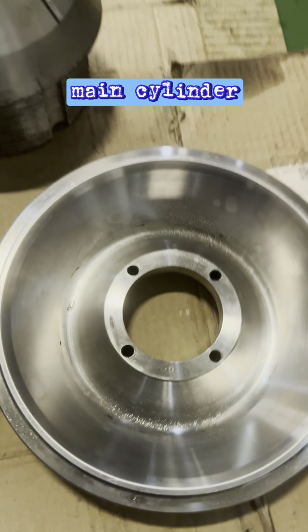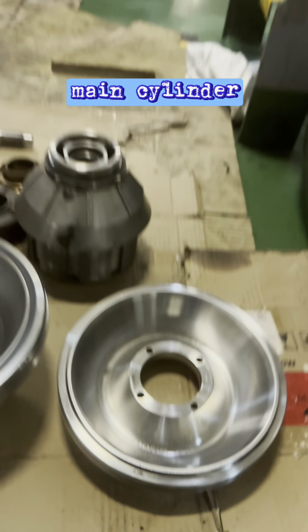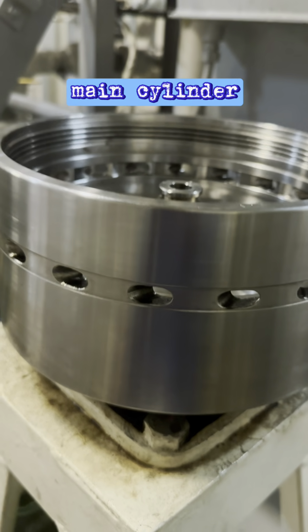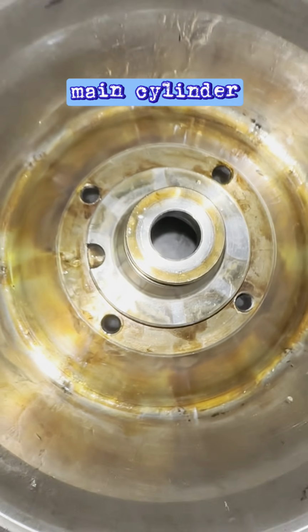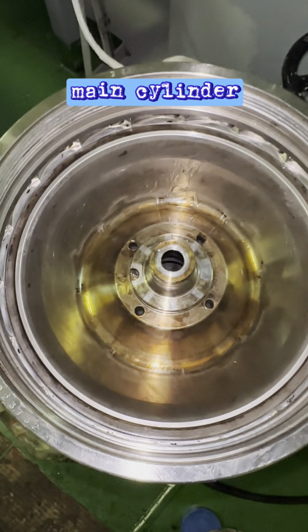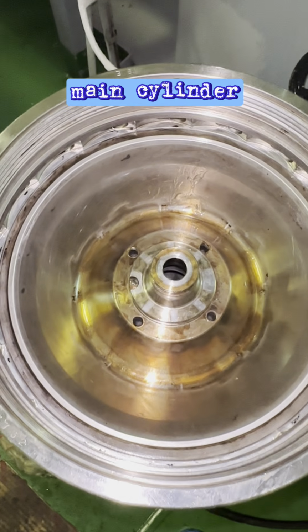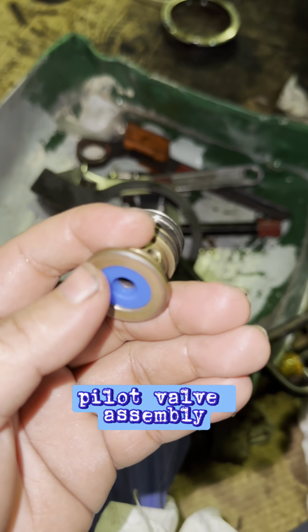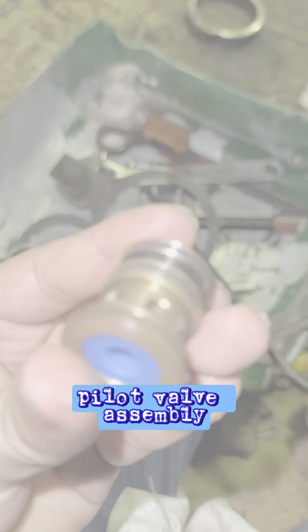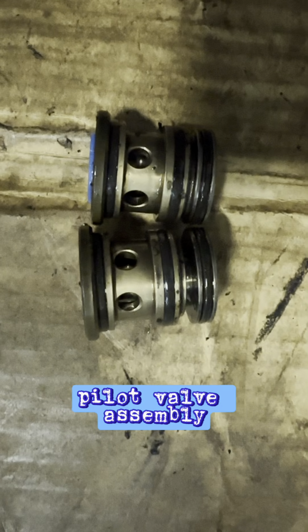The main cylinder keeps the bowl closed tightly during operation and will only open to release sludge and other contaminants accumulated on the periphery of the bowl. Pilot valve assembly, used to direct the operating water, keeping the main cylinder closed or open during operation.